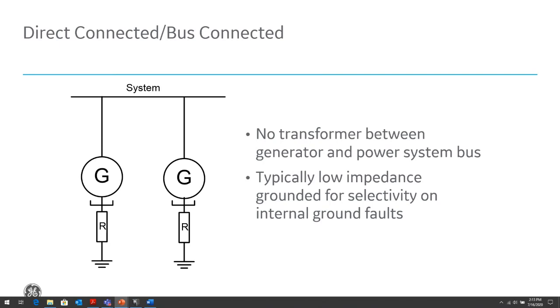The disadvantage of using this system is the generator is likely to be permanently damaged by an internal fault current. Because again, it's a low impedance ground, so if we have an internal fault in the generator, we'll see high ground fault currents and it's susceptible to being permanently damaged. The other problem, especially if we have two generators connected to the same bus, is to discriminate which generator that ground fault is on. So if the generator on the left has a ground fault, both generators will see ground fault current because they're both grounded through low impedance ground.